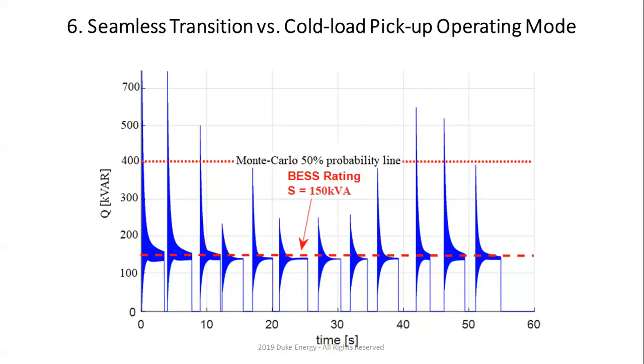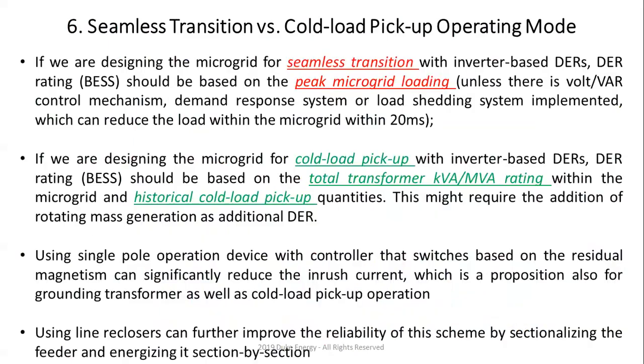So that means that when you design the battery, if you want to do cold load pickup, you have to do a whole lot more than if you're just doing seamless islanding. Because when you do seamless islanding, the only thing that you have to worry about is the inrush current to the grounding transformer. When you do cold load pickup with battery plus PV, then you essentially have to worry about every single transformer that's in your system, right? And you probably know the size of the transformer can be 3-4 times the maximum load. So now you have that thing going against you, right?